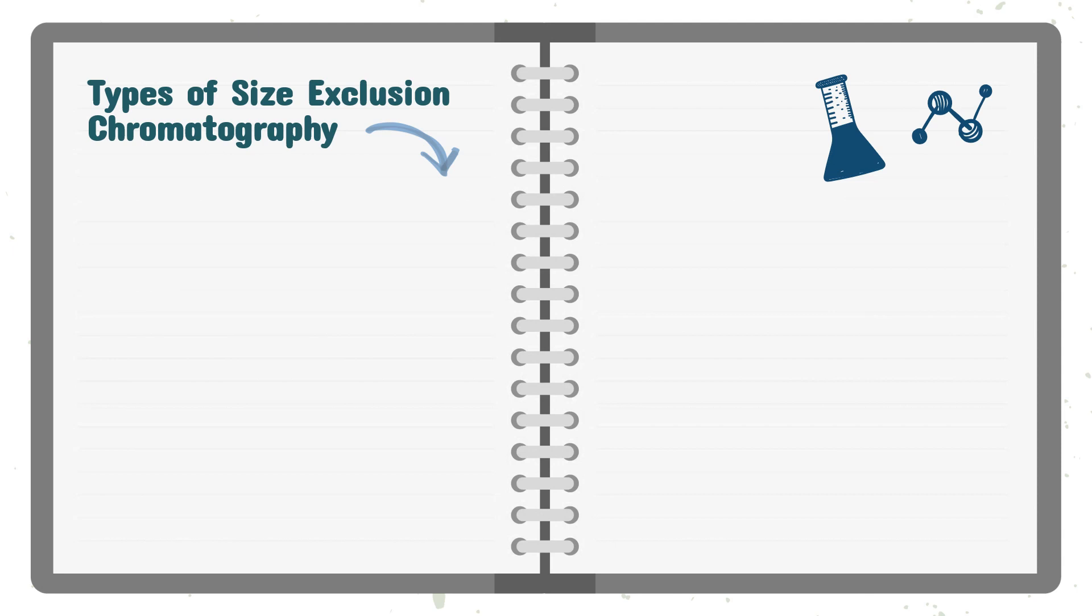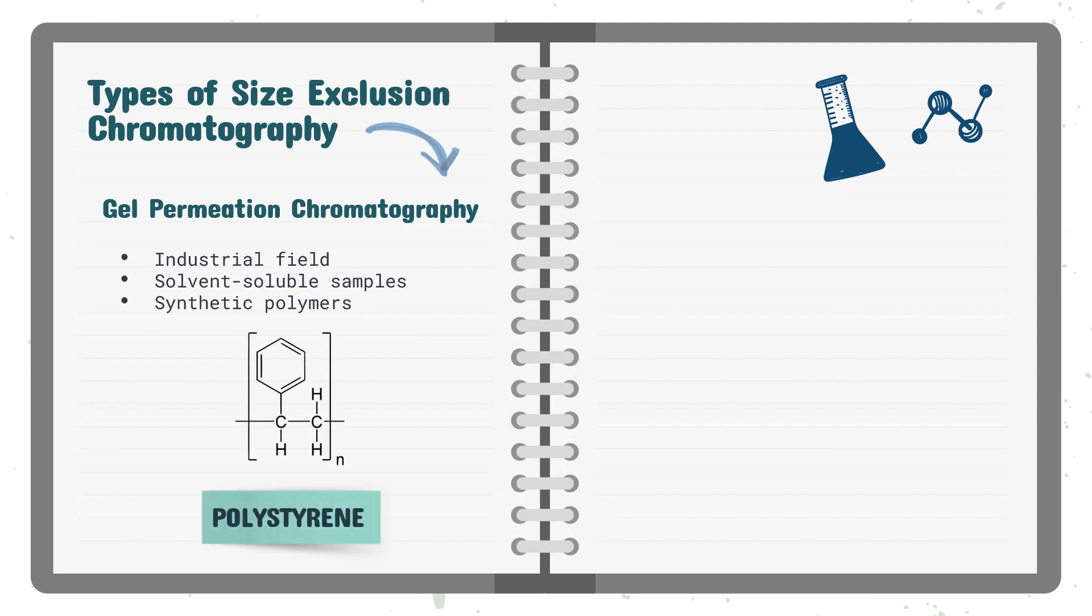There are two types of size exclusion chromatography. One is gel permeation chromatography, which is usually used in the industrial field. It uses cross-linked polystyrene polymer packing material and a nonaqueous mobile phase to separate and measure the molecular weight distribution of solvent-soluble samples such as synthetic polymers. The standard used for calibration is polystyrene.